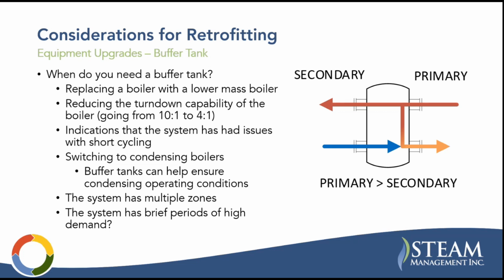Buffer tanks also help promote condensing operation, they help buffer system spikes, and they make it easier to control your system. If the system has multiple zones, the buffer tank smooths out demand spikes. And if the system has brief periods of high demand, that's another indication. Buffer tanks can act as your decoupler, which I mentioned as well, so you want to put it in that decoupler line on a primary secondary system. It also can be a point for air removal, so you may eliminate the need for a separate air separator. They're a pretty good thing to consider when you're retrofitting.